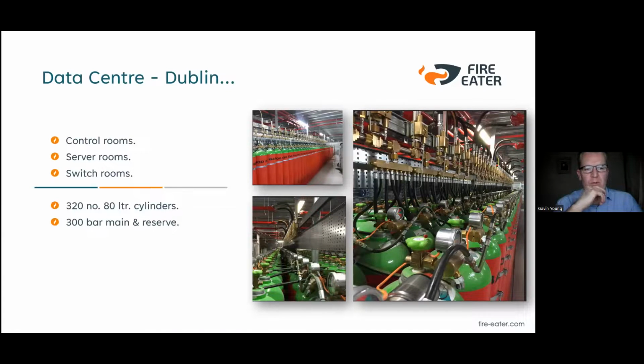This is actually the first project I did, back in 2013. It's a data center in Dublin. It was a pretty big one to put your teeth into, so it's got 320 80-liter cylinders. There were 8 data halls on a directional valve system, so there are enough cylinders there to protect the largest risk. And it's a shared system, so it protected, as I said, 8 data halls, but also, I'm not too sure, something like 10 switch rooms. If a switch room activated, it would take the required amount of cylinders from that cylinder bank and discharge the relevant amount into the switch room.